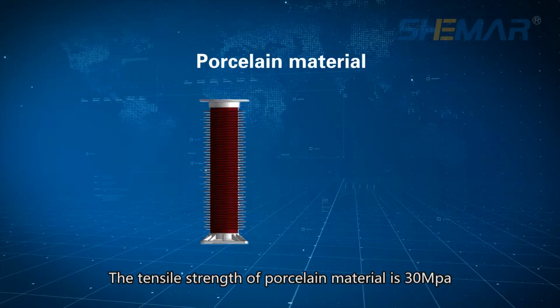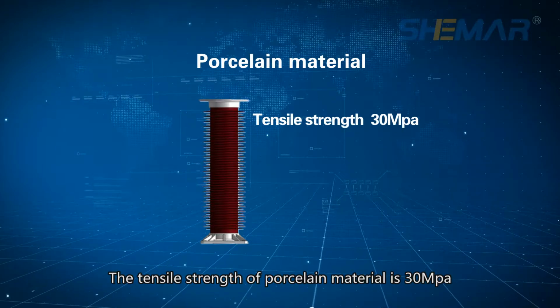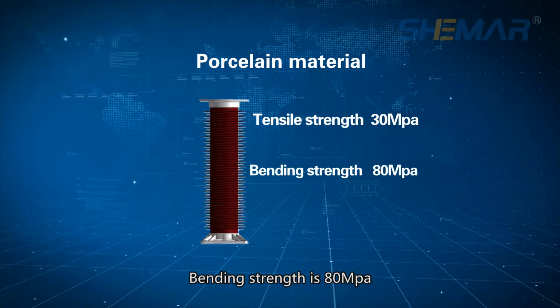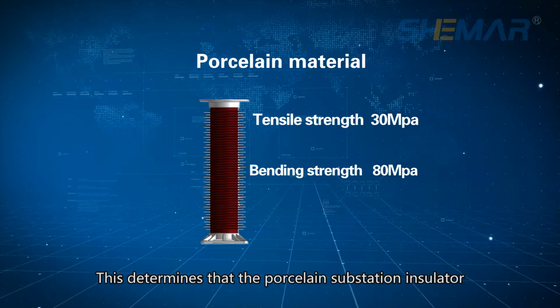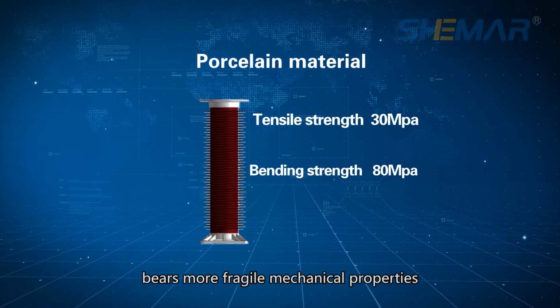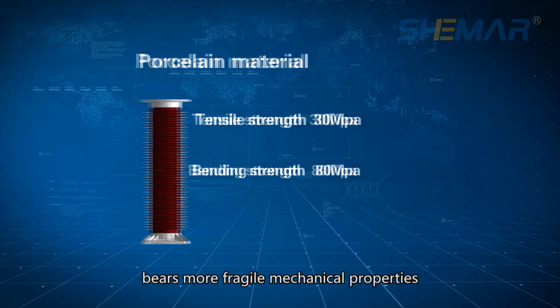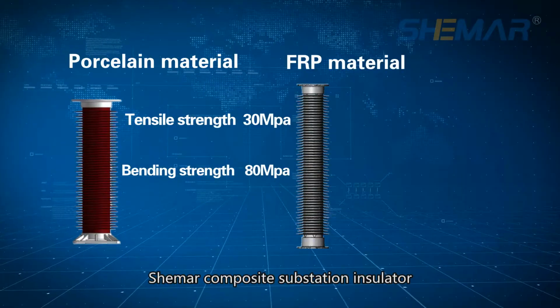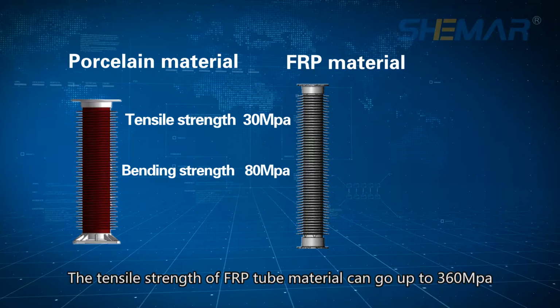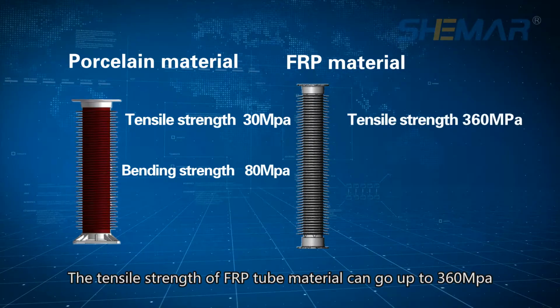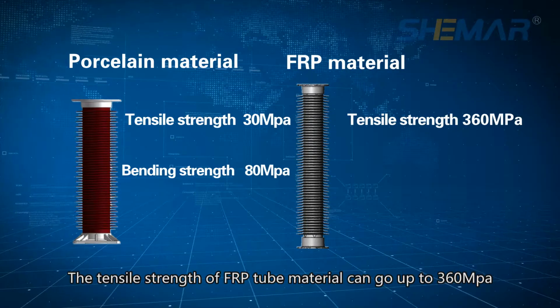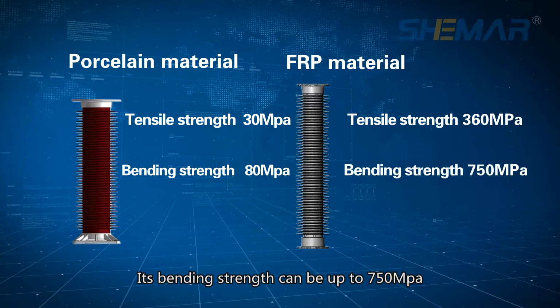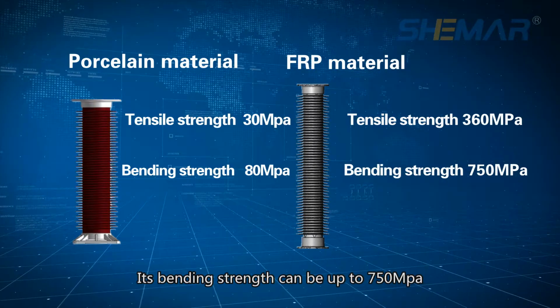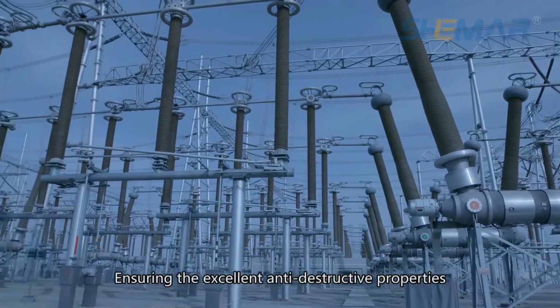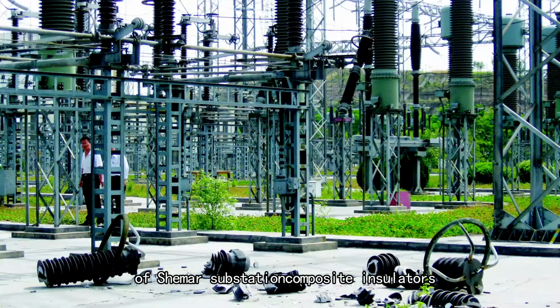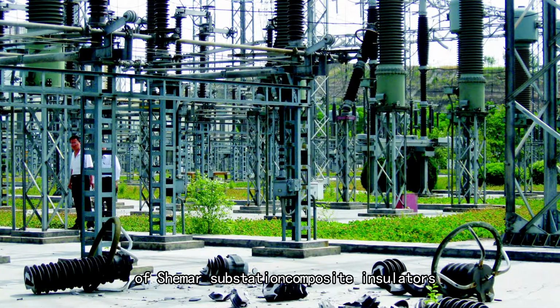The tensile strength of porcelain material is 30 MPa, and its bending strength is 80 MPa. This means porcelain substation insulators have more fragile mechanical properties. SHEMAR Composite Substation Insulator's FRP tube material has tensile strength up to 360 MPa and bending strength up to 750 MPa, ensuring excellent anti-destructive properties.